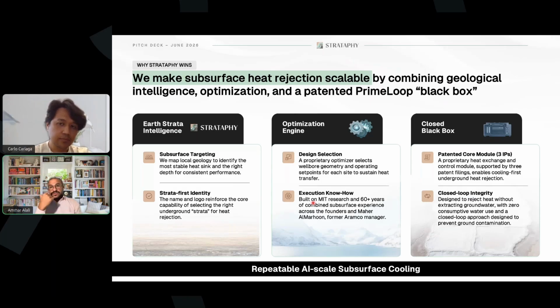It's counterintuitive, because we're used to cooling demand for buildings, commercial, industrial, residential, you name it, being a function of the thermal energy inside, which is influenced by how hot it is outside. At night you have lower thermal load, during the day it becomes hotter. Data centers have the thermal load inside, so inside the data center the thermal load is high and it doesn't really fluctuate.